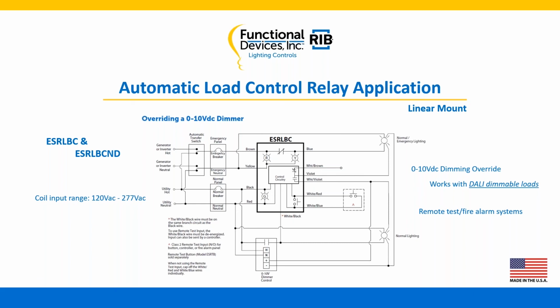In the DALI world, you're basically using the violet and the white-brown to make a connection, because in the DALI world, you are passing along a current and power at that point. A little different, but it's the way they work. Again, we've got a remote test in this. Our voltages on this, as we mentioned earlier, are 120 through 277. Everything pretty much lines up pretty well. We're very excited about this new product, and look forward to moving forward with everybody.